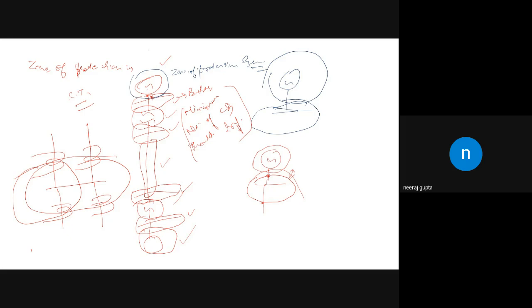So each of the zones can be implemented by different relaying principles. Sometimes we use different relays for the implementation of different types of zones. Like if you take the case of the bus bar, because the ends are near, we use differential protection. However, for this transmission line, we use distance protection. So you cannot say that all the zones are perfectly marked out. The zones keep on expanding or contracting depending upon the system conditions.